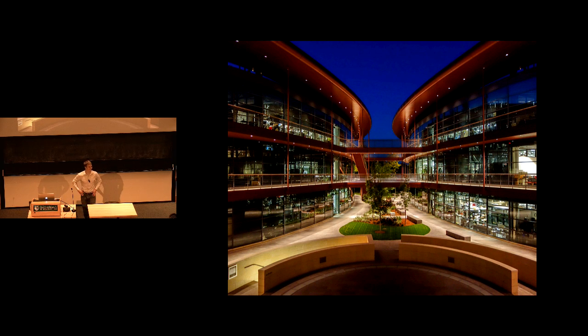That would be my next question. What was your field of view? Our field of view depends on the objective lenses that we're using, but we're designing around a 16x objective, where we can hit about 750 microns square. And with a 25x objective, it gets down to about 350 microns. Then we're looking at potentially working with manufacturers to develop custom optics that would allow us to hit wider fields of view, where we could again sacrifice resolution for increasing the number of cells that we hit.